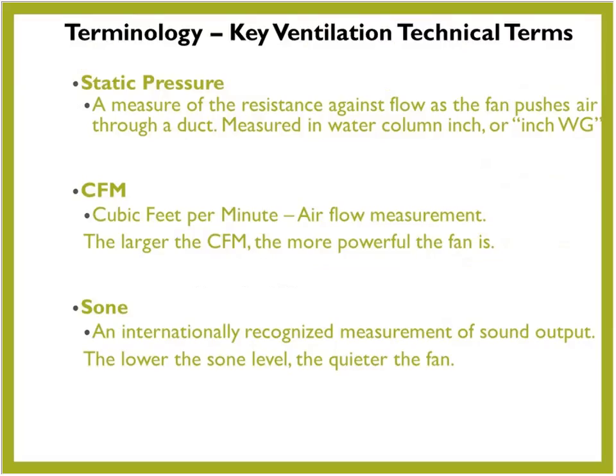Okay. Again, this presentation is called Introduction to Ventilation. Some of this information you guys already know. CFMs, cubic feet per minute, you know about sones, the noise level that a bath fan or a piece of ventilation equipment makes. Again, these are tests that HVI does and gives us information so that we can publish that information about our equipment. I always like to use a reference for sones. If you walk out in the kitchen in the middle of the night when it's quiet and you can hear your Energy Star refrigerator running, that's about 1 sone. And that's kind of the standard for bathroom ventilation these days, 1 sone or less. So just to give you a reference, that quiet hum that you hear in the middle of the night coming out of your Energy Star refrigerator is about 1 sone.